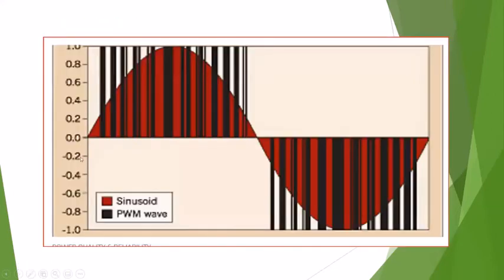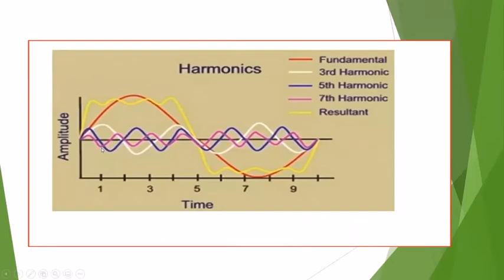And again, this is the output waveform, where we're firing the transistors of the PWM. This is the voltage going out to the motor, and the red is the resultant current going to the motor. So it's also important to utilize the higher-end drives that have the feedback. They're not volts per hertz. They're sensorless vector or vector control, so that we can really control these pulses properly to give us as clean a waveform as possible, which also gives us better torque.